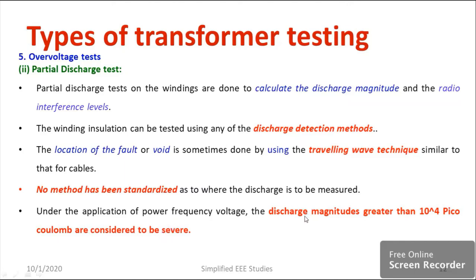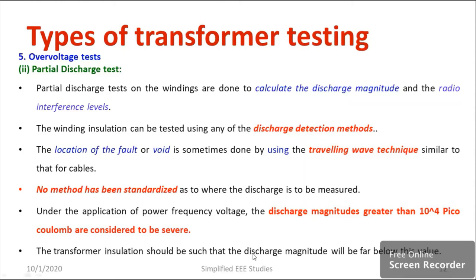After comparing with the waveforms in the discharge detection method, if you find the discharge magnitude more than 10^4 picocoulombs, there is a severe fault happening in your transformer winding and you must immediately replace it. In the case of a transformer, the winding insulation should be such that the discharge magnitude is less than 10^4 picocoulombs — if it exceeds that, there is something severe happening in the transformer winding insulation.